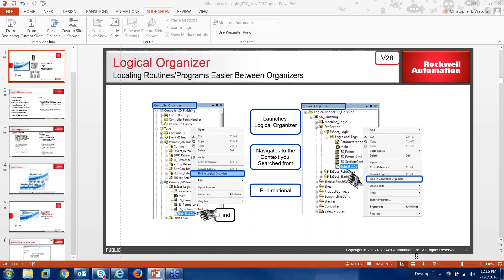The logical organizer enhancement is similar to what was introduced in version 24. By right-clicking in the Controller Organizer you can find a portion of logic and launch the logical organizer. From there you can navigate to and highlight where within the logical organizer that code is executed. It's bi-directional — you can toggle back and forth between your default and logical organizers while programming. Users on version 20 won't have seen this; version 24 users will recognize it as an addition.